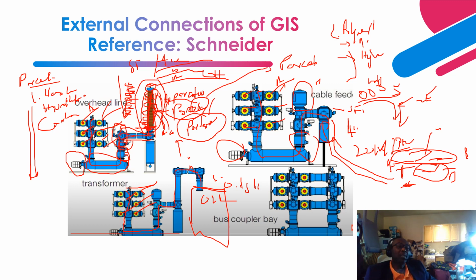And we utilize that scheme when we close the tie breaker is when we want to take one source out and have these two buses being fed with a single source. Under normal circumstance, when this one is open, this bus is fed from here, and this bus is fed from here.